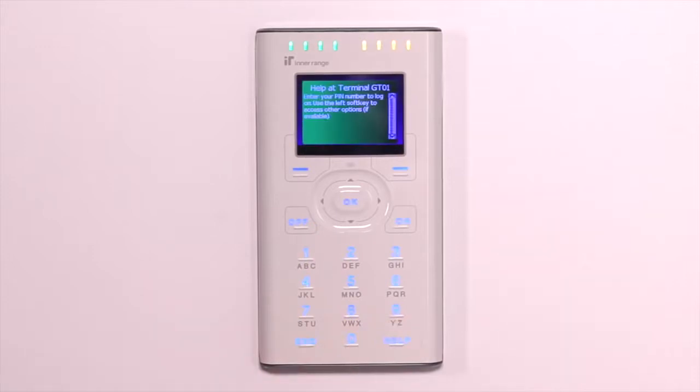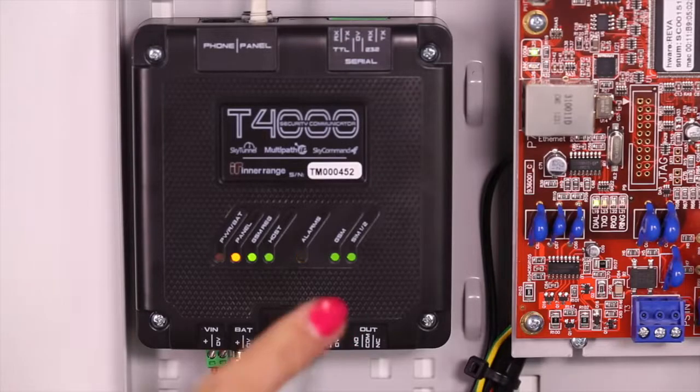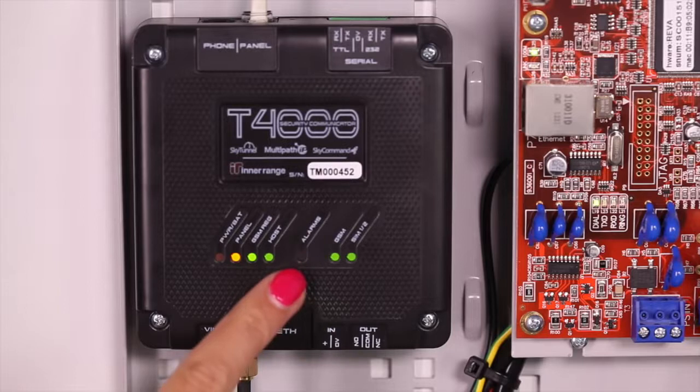Our T4000 is now fully enrolled and is ready to test. The best way to test your T4000 is to generate an alarm event and then call your monitoring station to verify that it has been received. Once you've generated an alarm event, pay attention to the alarms LED. When this LED lights up, it indicates that the T4000 has successfully received an alarm from the alarm panel. The alarms LED will turn off once the alarm has been successfully sent to the monitoring center.